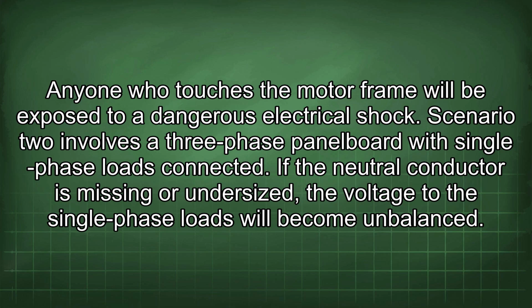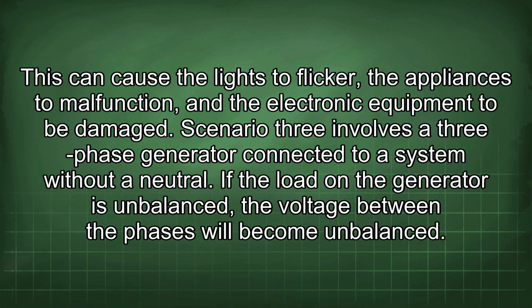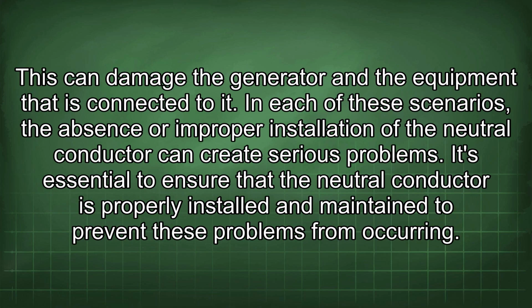Scenario 2 involves a three-phase panel board with single-phase loads connected. If the neutral conductor is missing or undersized, the voltage to the single-phase loads will become unbalanced. This can cause the lights to flicker, the appliances to malfunction, and the electronic equipment to be damaged. Scenario 3 involves a three-phase generator connected to a system without a neutral. If the load on the generator is unbalanced, the voltage between the phases will become unbalanced. This can damage the generator and the equipment that is connected to it. In each of these scenarios, the absence or improper installation of the neutral conductor can create serious problems. It's essential to ensure that the neutral conductor is properly installed and maintained to prevent these problems from occurring.